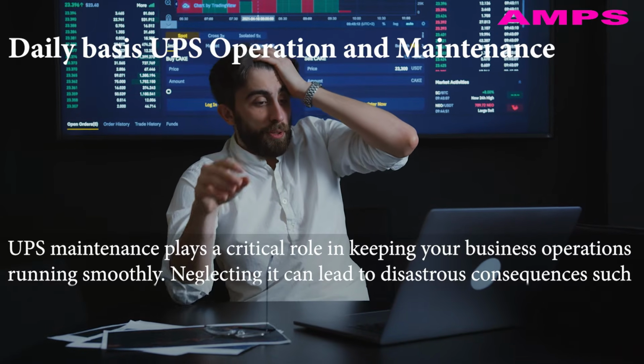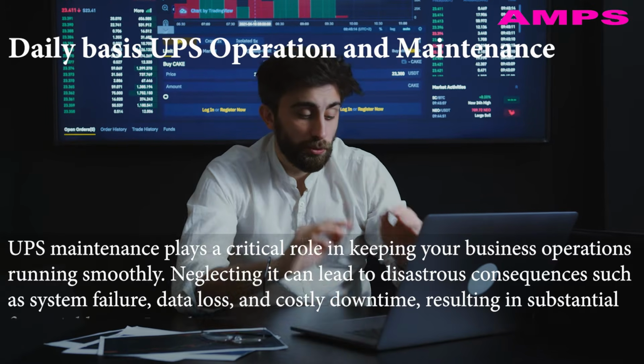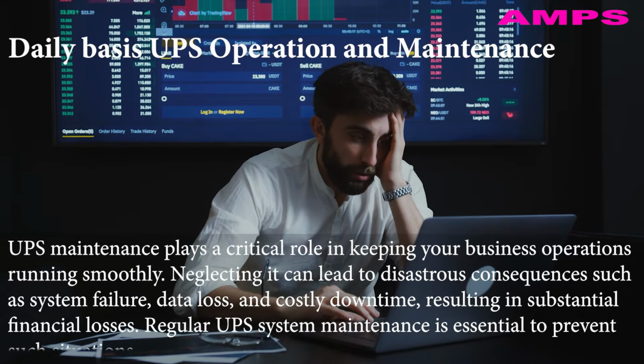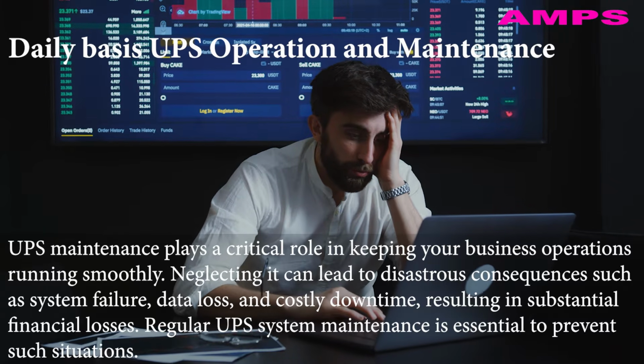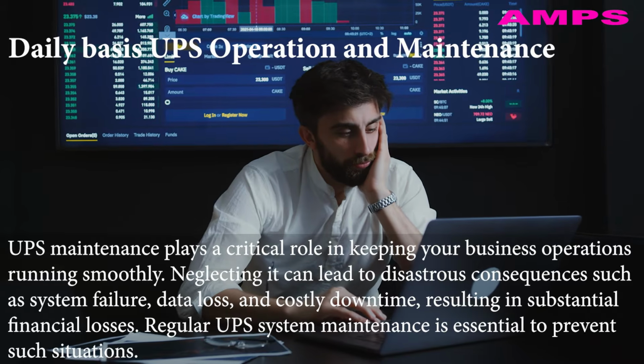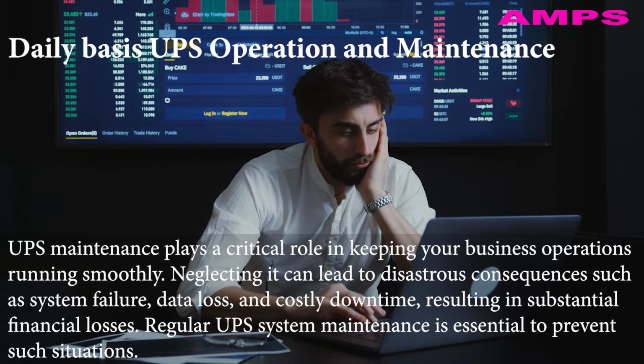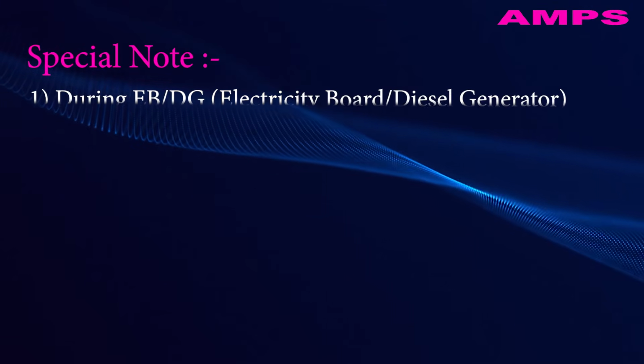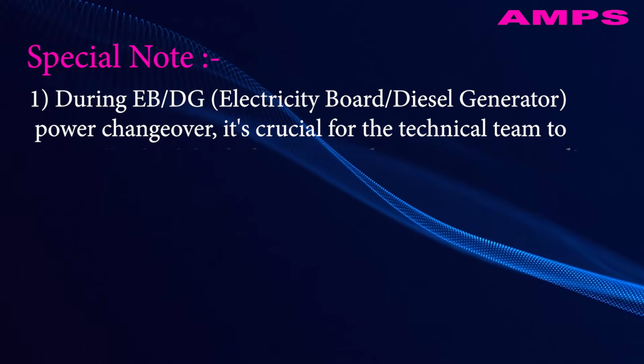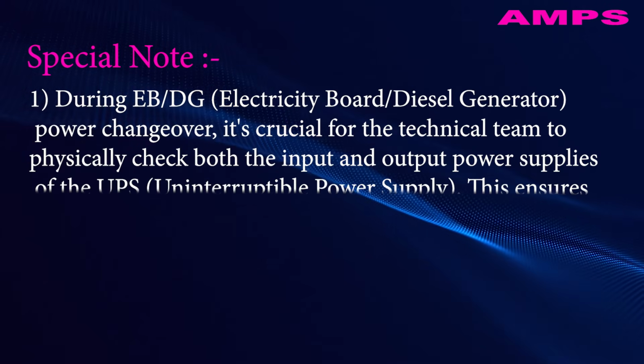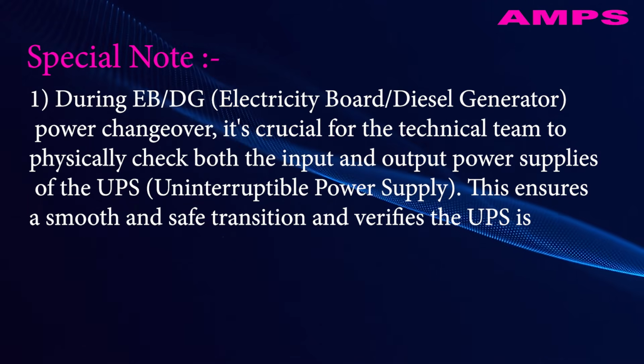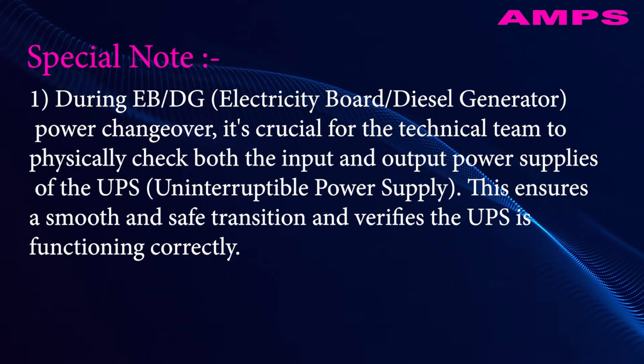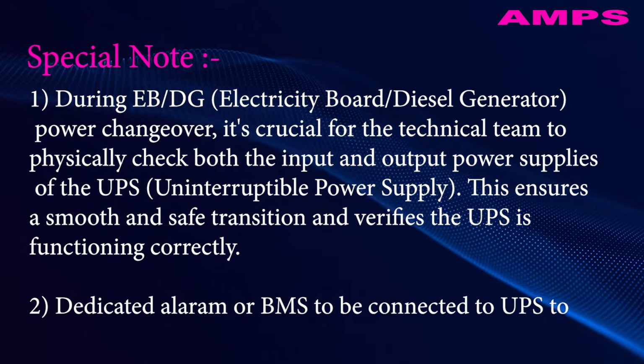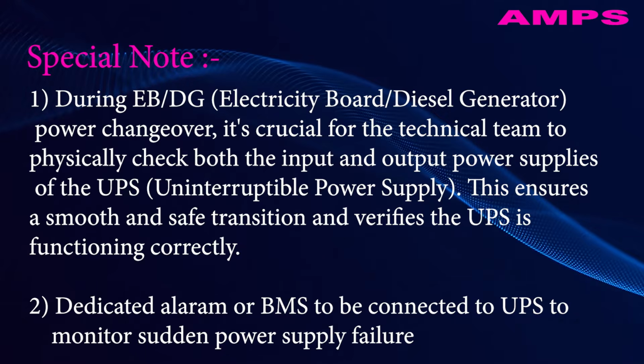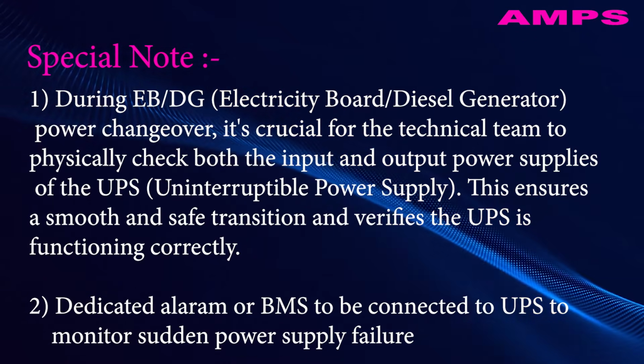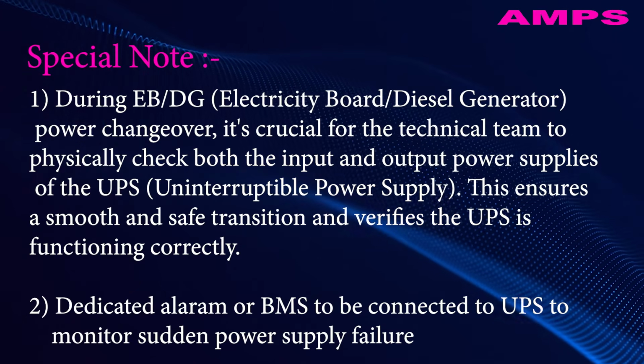UPS maintenance plays a critical role in keeping your business operations running smoothly. Neglecting it can lead to disastrous consequences such as system failure, data loss, and costly downtime, resulting in substantial financial losses. Regular UPS system maintenance is essential to prevent such situations. Special note: 1. During electricity board or diesel generator power changeover, it's crucial for the technical team to physically check both the input and output power supplies of the UPS. This ensures a smooth and safe transition and verifies the UPS is functioning correctly. 2. Dedicated alarm or BMS to be connected to UPS to monitor sudden power supply failure.